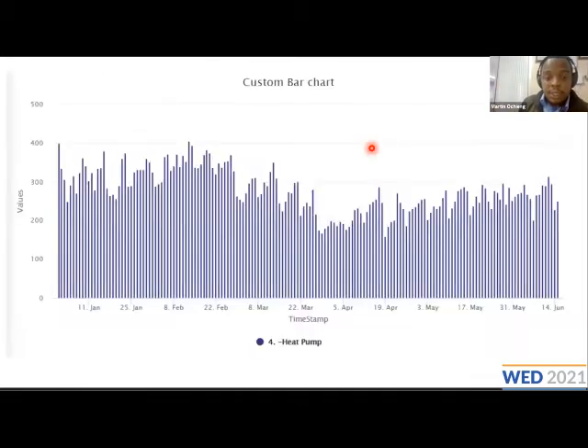And as you can see, drawing from energy consumption data from January up to around 14th June, there's a significant reduction in energy consumption generally on the heat pump itself, which has made it so that the heat pump as of now isn't the highest consumer. We've seen a significant reduction in energy consumption on the heat pump specifically, which is positive for this particular facility. So that indicates how we can use real-time energy monitoring data in conjunction with the human element, in this case an energy committee, to reduce energy consumption.